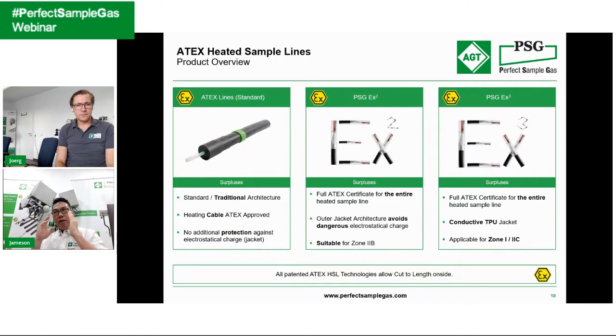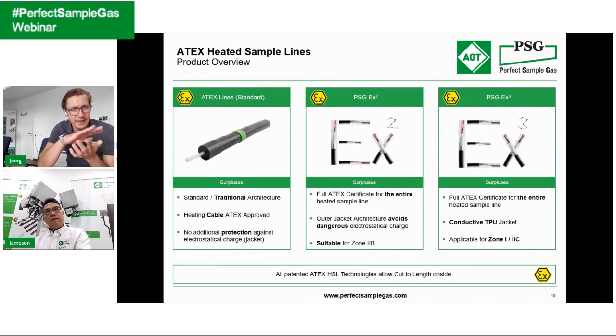So can we put ourselves in the consequences - the possibility - if a customer is in the petroleum industries, what are the things that will help them if they consider with and without a conductive jacket in terms of safety? Why should they choose a conductive jacket heated line? Yeah, I think if you can ensure that your line - this is the established concept, I would say - is everywhere grounded, for example via a cable tray, and these cable trays are grounded, if you can ensure this, and you're not extending a certain surface which is not grounded, I think you are even safe with a standard line.